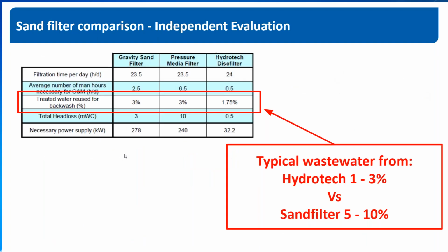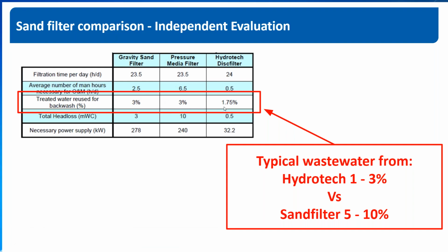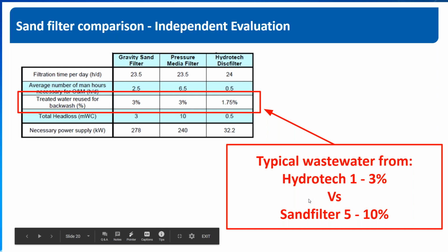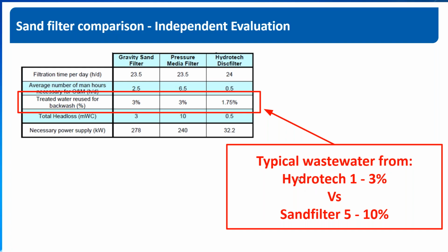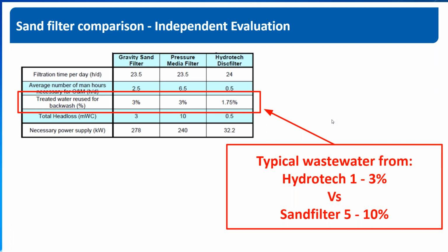Regarding sand filters at this Egyptian site, some of the highlights from this report showed that the amount of wastewater from backwash for a gravity sand filter and a pressure media filter was 3%, and the Hydrotech disc filter was 1.75%. The number that we see for the Hydrotech disc filter is what we normally see, so between 1 and 3%. For the sand filter, it's actually on the low side. What we have been led to believe is normally 5 to 10%. So you get decent savings in the amount of produced wastewater as a result of using a Hydrotech filter. This can be quite relevant when you're trying to improve your cycles of concentration at a cooling tower.